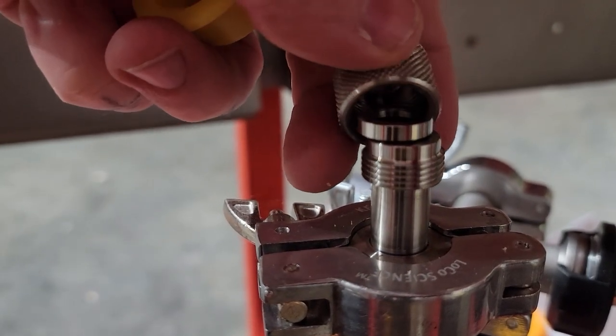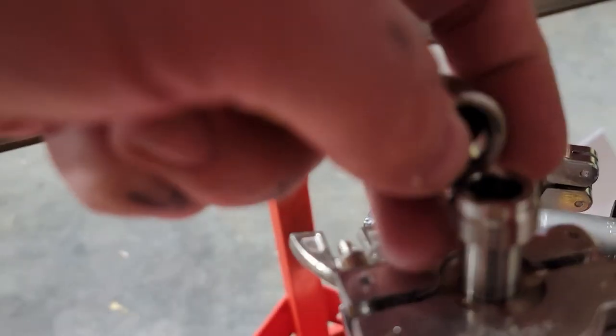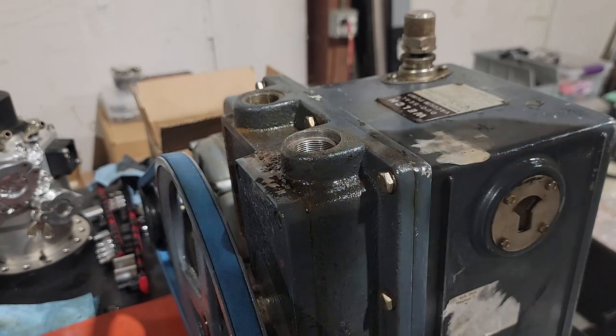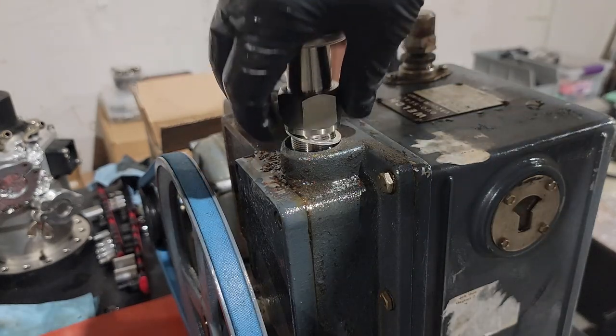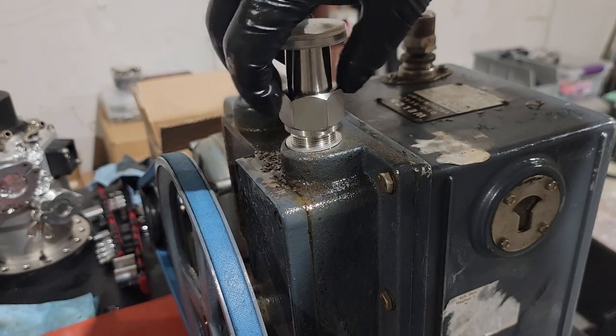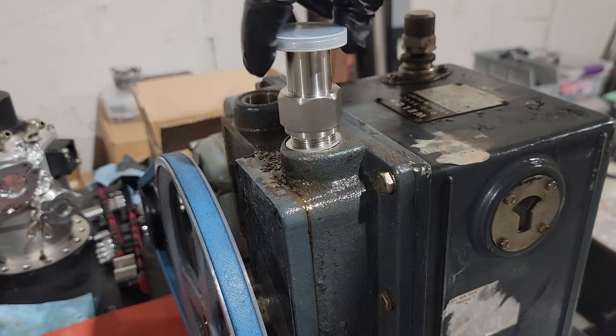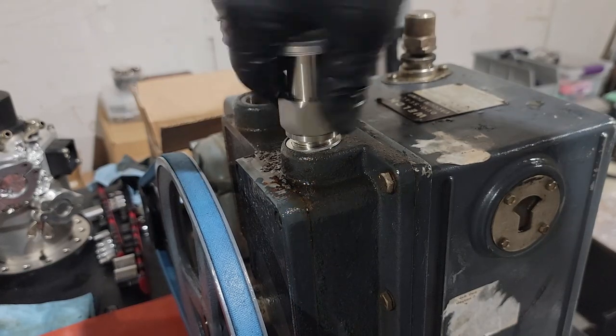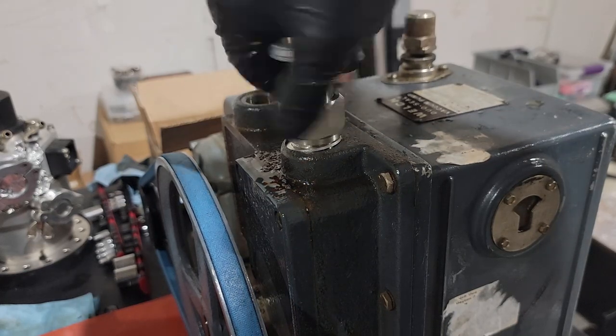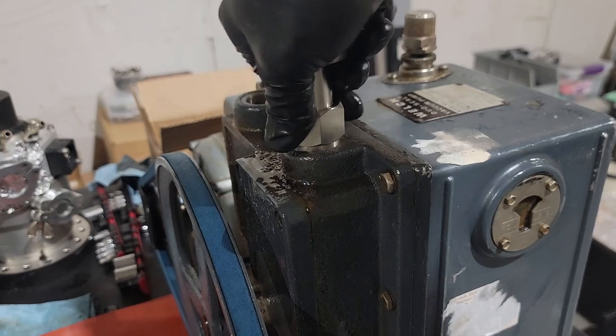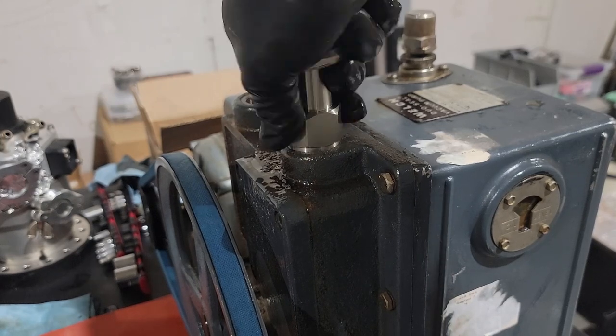Outside of these dedicated high vacuum flanges, you may see other fittings used in vacuum systems depending on the application. Sometimes compression fittings are used, especially at the interface between glass and metal components. Sometimes, although rarely, you'll see pipe threads used in vacuum systems, but usually only where they'll be exposed to rough vacuum and not high vacuum. Threaded fittings are difficult to vacuum seal, even to rough vacuum, but they can be sealed with a high-quality Teflon tape or with a type of vacuum sealing wax.